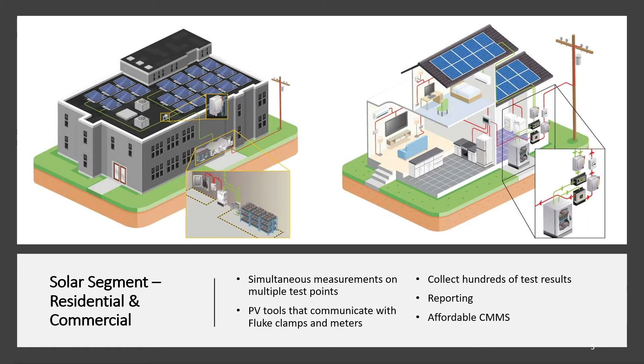But when we get into that solar or utility aspect, it's very large, very capable, with a lot of voltage. Typically in our world, residential ran at 600 volts, commercial at 1000 volts, and utility level jumped up into that 1500 volt DC range. We're now seeing those voltages step up even more—residential getting close to 1000 volts, commercial jumping to 1500, and there's talk of even going to 2000 volts or higher on some utility levels. Incredible voltages, very large systems.